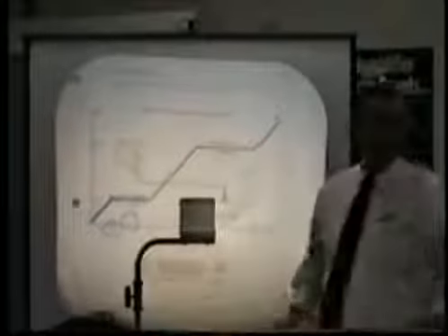Okay, here we go. So if I go from a pound of 32 degree ice and warm it up to 32 degree water, how many BTUs did it take to do that? And the answer is 144. Wow. 144 BTUs to change the state. No change in temperature.